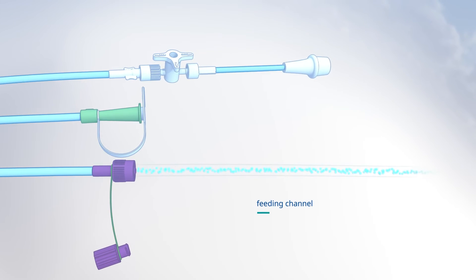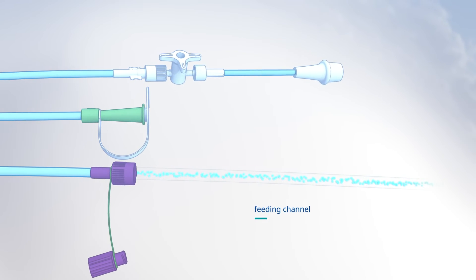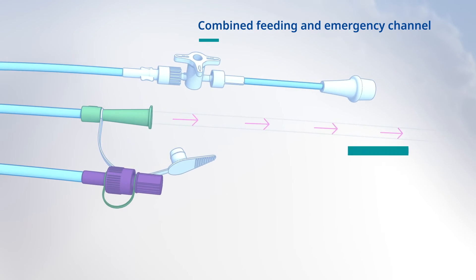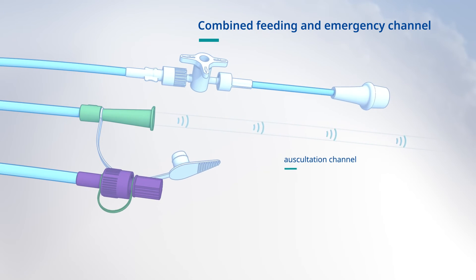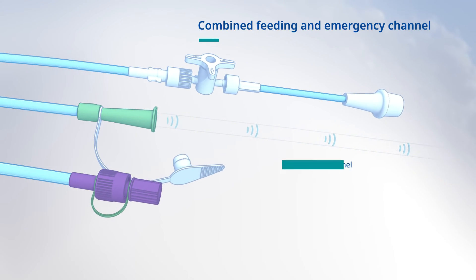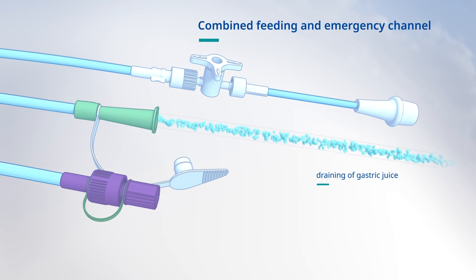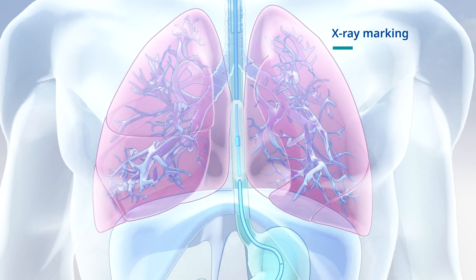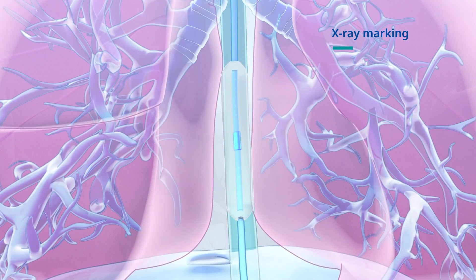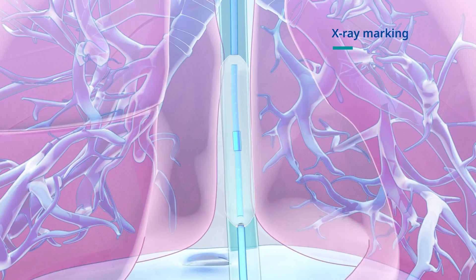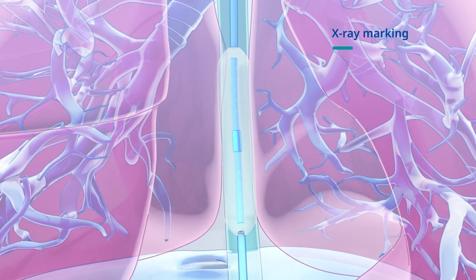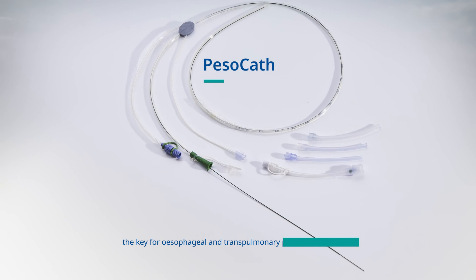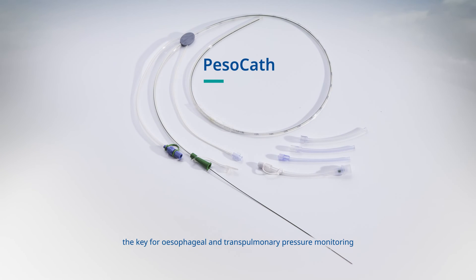The combined feeding and emergency channel permits auscultation during catheter placement despite the ENFIT connection. In an emergency, this can be used as a direct channel for rapid suctioning or for draining gastric juice. Because of the non-metallic X-ray markings, the esophageal catheter does not have to be removed prior to MRI diagnosis. PesoCath — the key for esophageal and transpulmonary pressure monitoring.